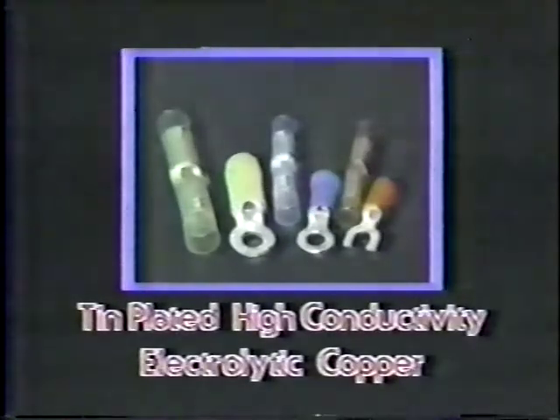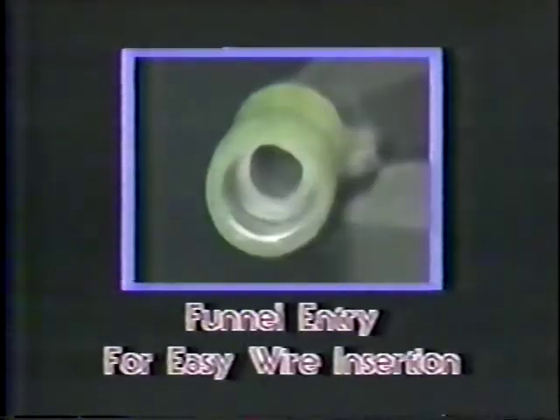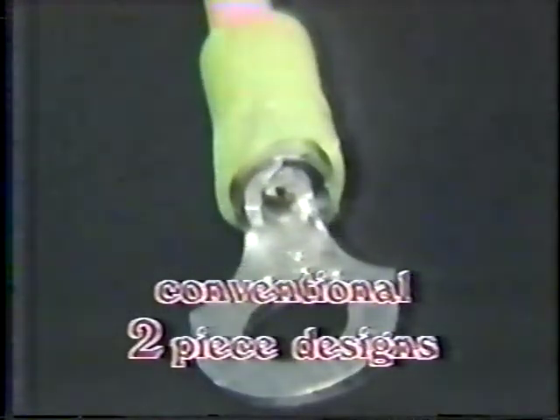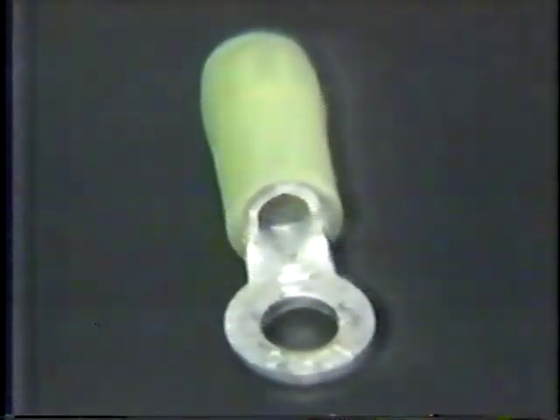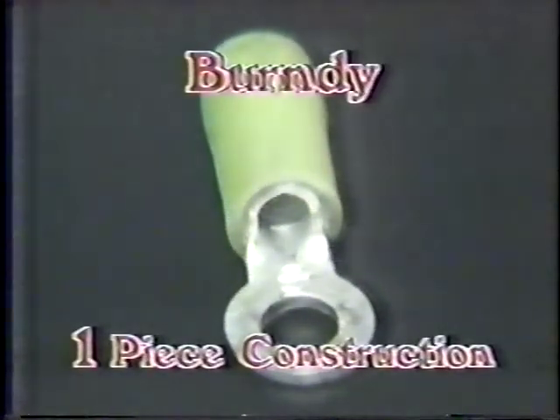Superior installation tooling is only the beginning of Burndy's small Hy-Dent story. Our terminals and splices have features that are unmatched by competitive products. They're made of tin-plated high-conductivity electrolytic copper with deep serrations in the barrel to resist pull-out. They also feature a funneled entry for ease of wire insertion. Unlike conventional designs, which can easily be damaged by an off-center crimp, Burndy's terminals feature a one-piece body construction with a fully brazed seam to prevent folding and splitting.